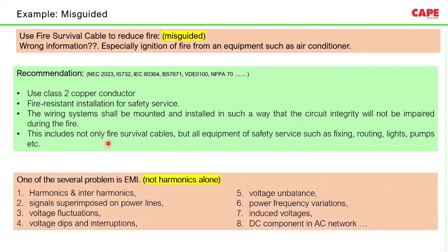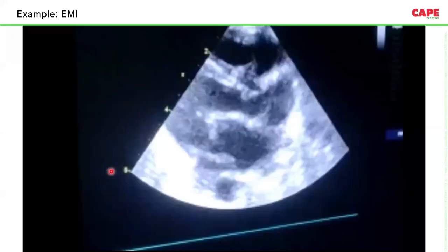Another issue is EMI. I would say harmonics is one of the subjects in EMI, especially in the hospital. There are several issues: harmonics and interharmonics, signals superimposed on power lines, voltage fluctuation, voltage dips, voltage unbalances, power frequency variations, induced voltages, and so on. There are several issues because in a hospital, a lot of equipment is used.